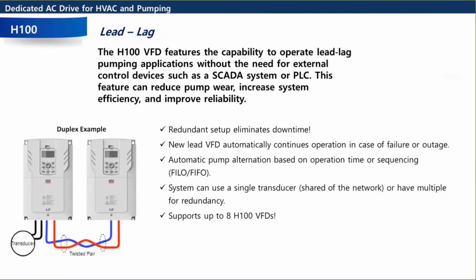You set the drive addresses to 1 to 8, and then the drives are automatically going to regulate the pressure. They're automatically going to stage and destage based on what's required. So do we need to run 1 drive, 2 drives, all the drives? And then they'll also automatically alternate. So every 24 hours, you could have them alternate, or you could change it to be whatever you want. You could have them alternate based on first in, last out, first in, first out. That's what the FILO and the FIFO is.